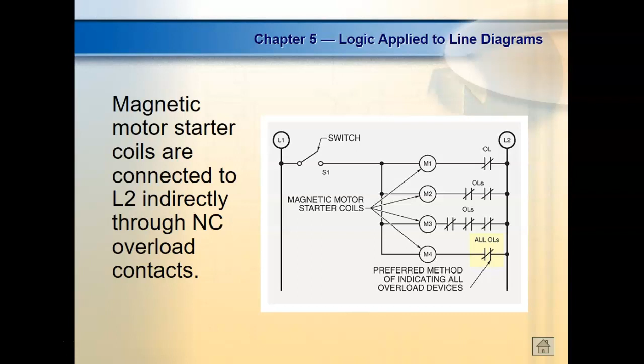So those basically are the guardians saying, hey, you can't put that much current through here. Because do the devices before it know what they're doing? Not really - they're just there to pass the current along. So we connect motor contacts before we put in overload contacts. That's pretty much the reason why.